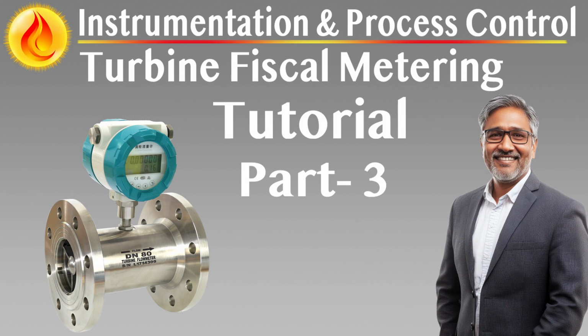Sampler. Representative composite sampling for laboratory analysis and custody validation. A flow proportional automatic sampling system must be installed on the metering station's inlet manifold to collect representative liquid hydrocarbon samples over a defined measurement period. The system must be of the grab type, actuated by discrete impulses from the station microcomputer. Each impulse must trigger a sample extraction event, with the cumulative sample forming the basis for quality analysis and net oil computation.